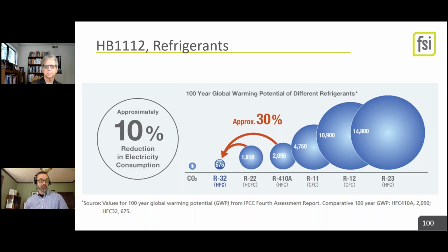At that higher pressure, it's more likely to leak, so you need more robust fittings, and it goes down the line. So it's largely a cost issue right now. That's why we're not using CO2 as a refrigerant more often, particularly in split systems. I'm not sure we ever will at large scale because we'd have to run such robust tubing.